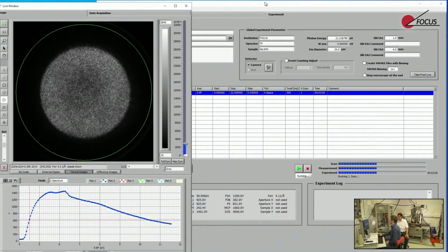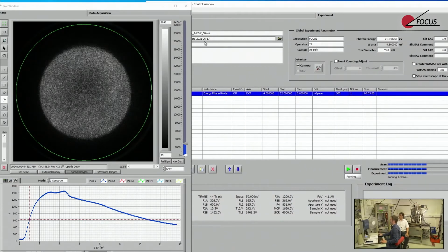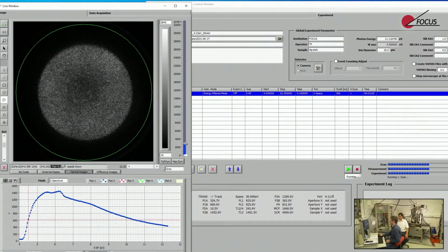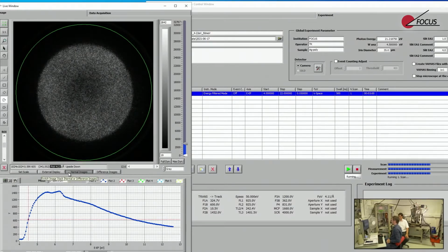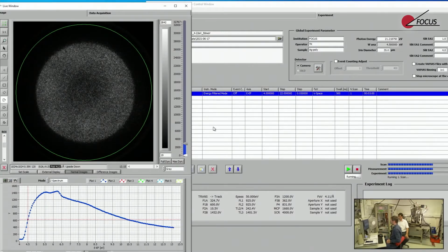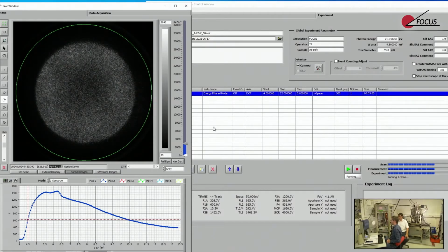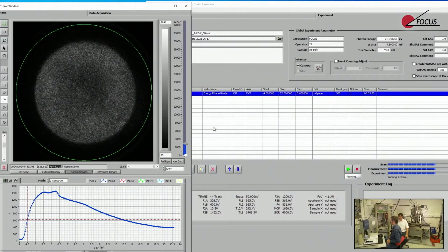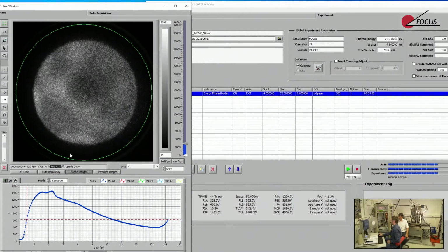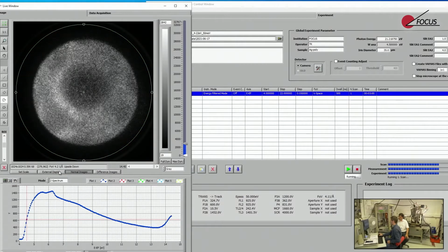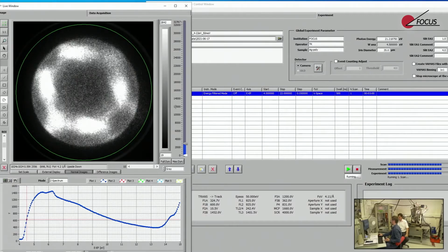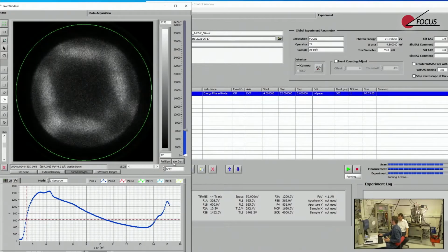But you could, of course, go a little bit more to the field of view chosen. So I've chosen a field of view of around four reciprocal angstroms, because this is what we are filling out with 21 electron volts. So if you have a source of higher energies, you would choose a larger field of view. So let's say with helium 2, you could go higher. However, of course, you could zoom in down to one reciprocal angstrom or even lower, and then move with the second stigmator to the feature you're interested in.